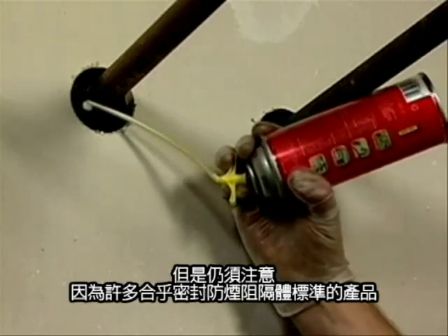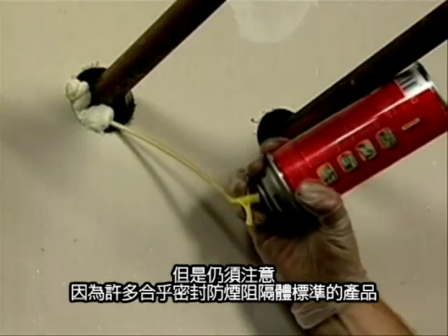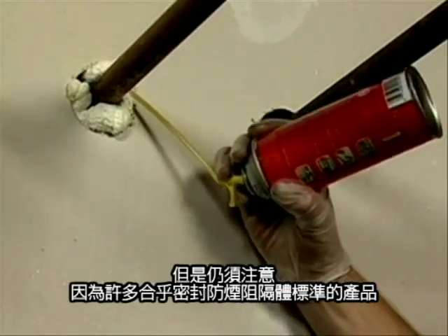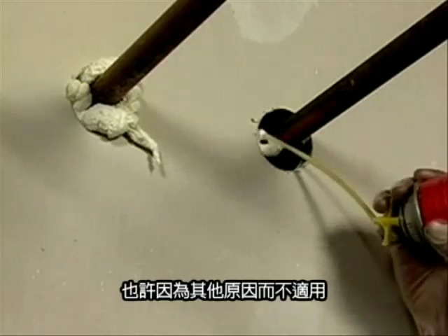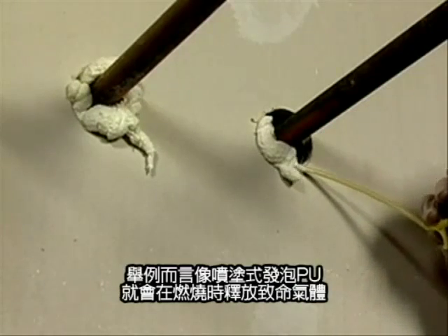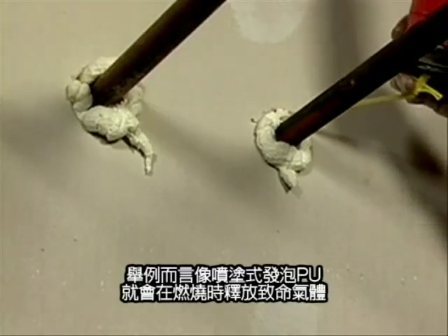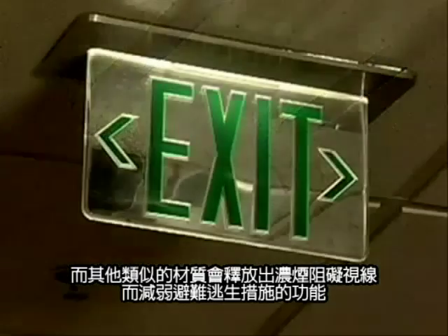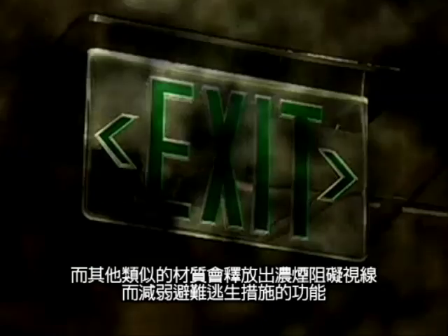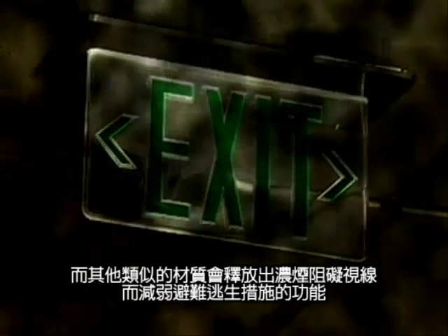Caution should be exercised, however, because many of these products that meet these standards for smoke barriers may be inappropriate for other reasons. Spray polyurethane foam, for example, can release lethal gases during combustion. Other common materials may release black smoke which obscures vision and impairs the means of egress.